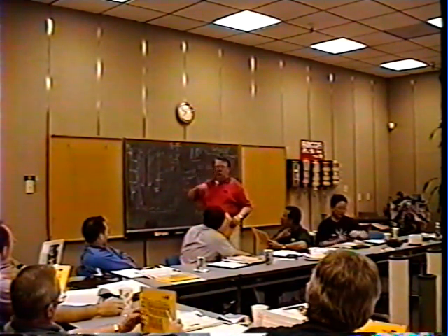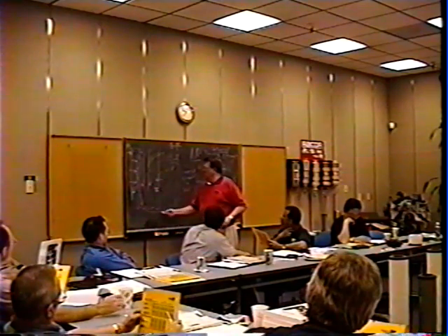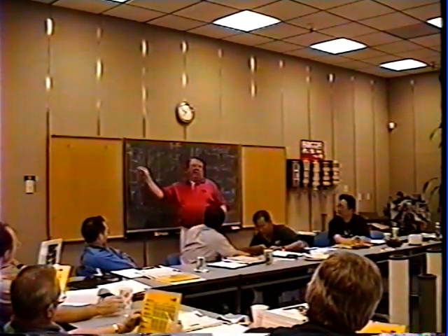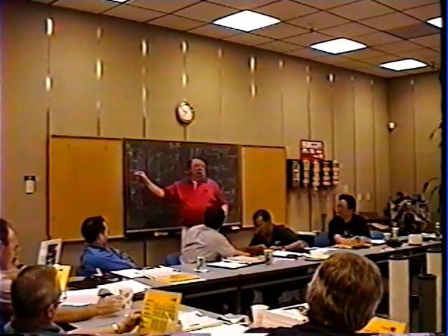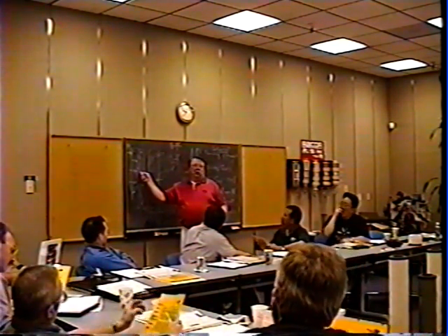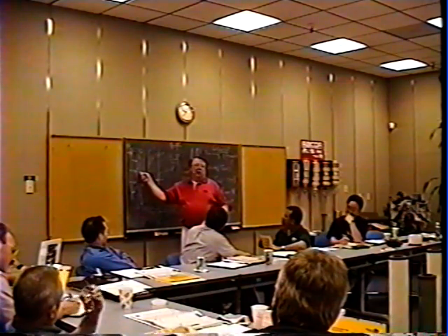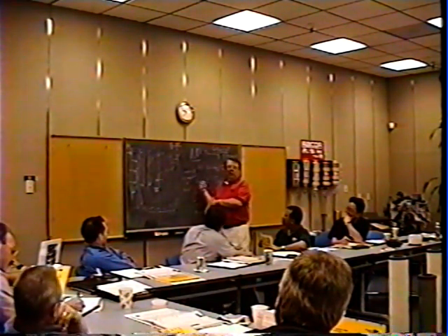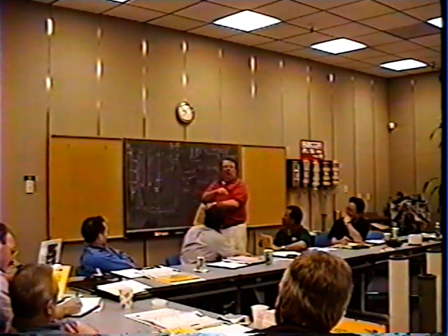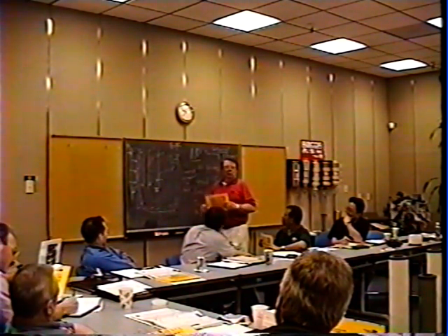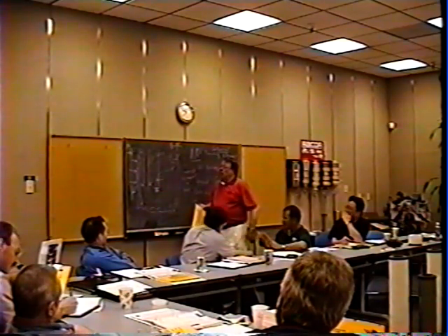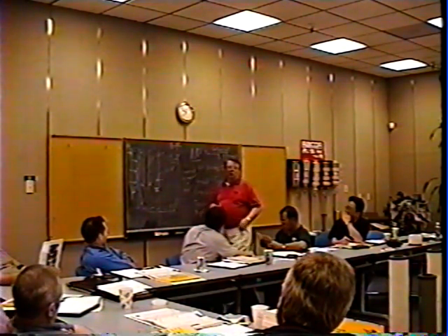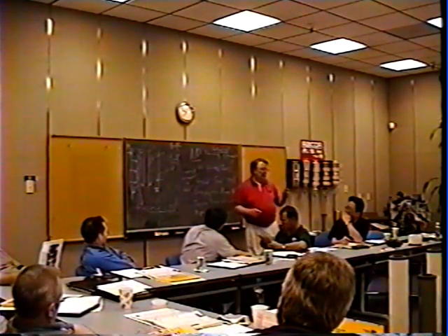Now, if this was a true coalescer, we would come in here and out there because we want to flow inside out. That means when your customer installs this and uses it this year as a trash filter, and next year he takes it over and puts it on his diesel fuel tank, then he'd have to replumb the whole unit. Here, you only plumb it up once, and then you can change elements any way you want. That's why it's a very versatile unit.